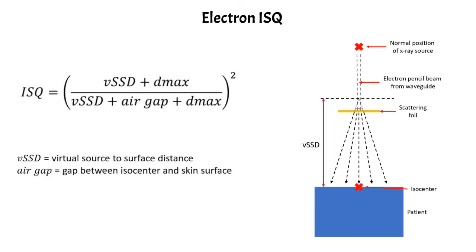And the virtual SSD is actually a function of the electron beam energy and also the size of the cone that you're using. So you have to measure it for all of the different energies and all of your different cone sizes as well.